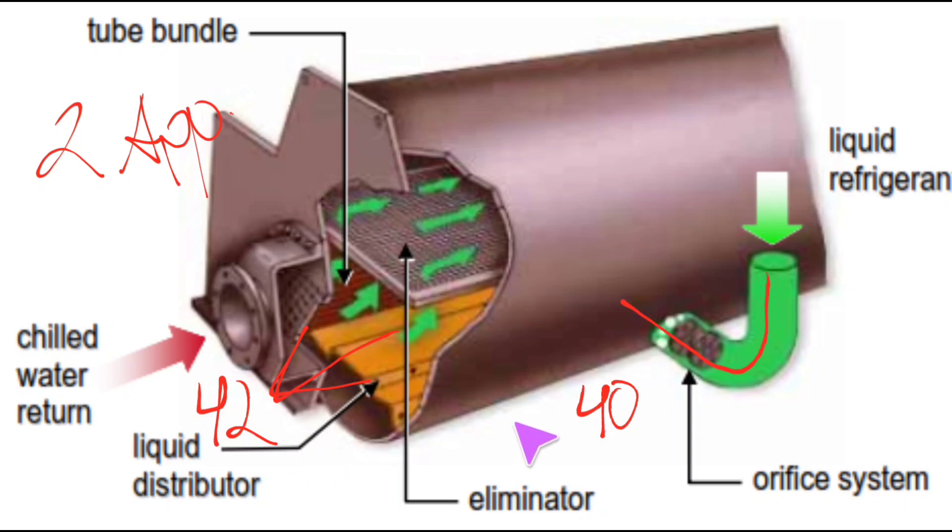What we have to focus on is, okay, what does it mean when we look at these numbers? Well, your saturation temperature on your evaporator side is always going to be lower than your actual water temp, and vice versa on the condenser. What we're trying to understand is how well are we transferring that heat, because we do have a design spec that we need to meet, and that's also going to play a huge part in our efficiency as well. End of the day, the lower the approach value, the more efficient you're operating, the better you're transferring heat. Ideally, if you could run a zero degree approach, you're doing perfect.